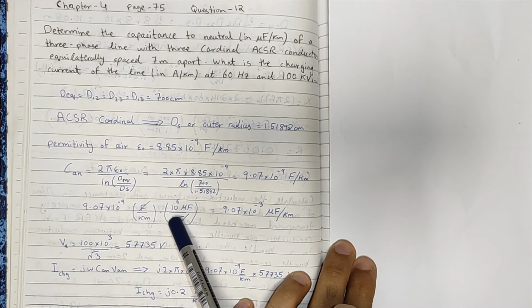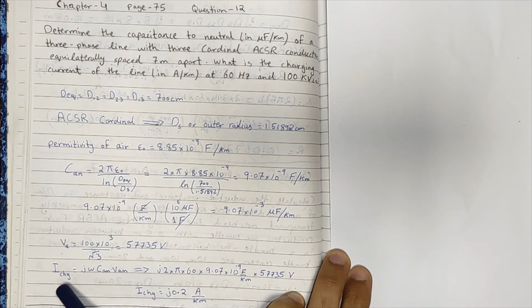Now the line-to-line voltage in the question is given as 100 kV. We will convert it into phase voltage or VA by dividing it by square root of 3, because we will be using the phase voltage to calculate the charging current. The formula for the charging current is I charging equals j omega capacitance to neutral and voltage to neutral or phase voltage. So we already know j, and 2 pi f will be used instead of omega. 60 Hertz is given to you in the question.